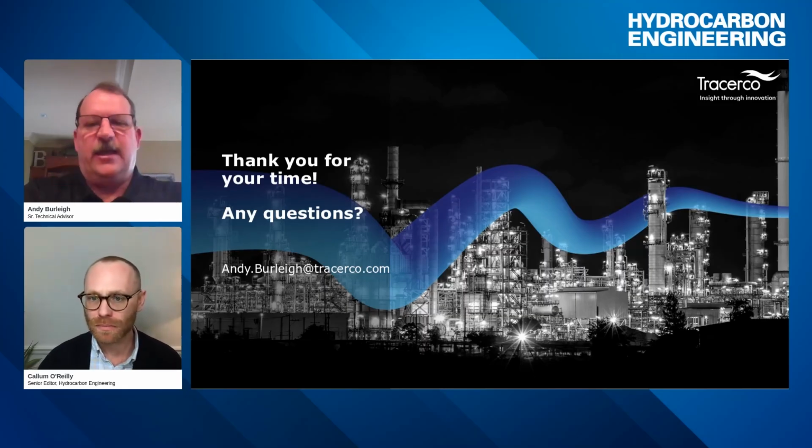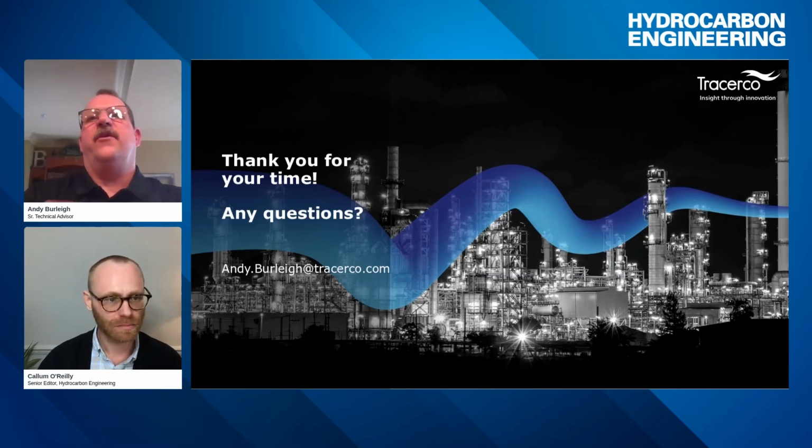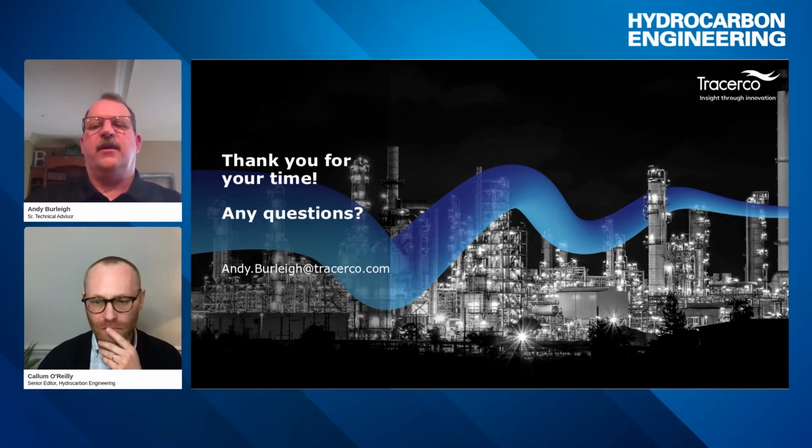Oh, excellent. That's an excellent question. We were kind of pressed for time, so I didn't get to cover that exactly. But to answer your question, the short answer is yes, there are limitations to the size. Things with very large diameter, also limitations with thickness of walls that we're shooting through or density of the material that we are potentially scanning through can all affect if we're able to get enough radiation through when we're talking about scanning.